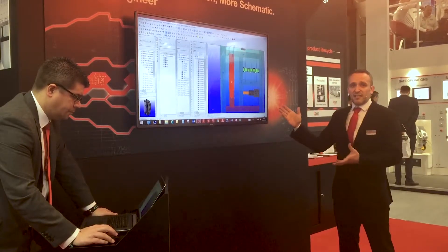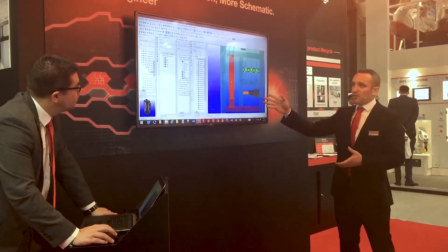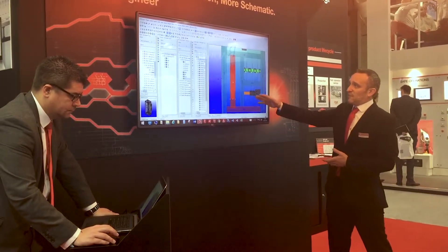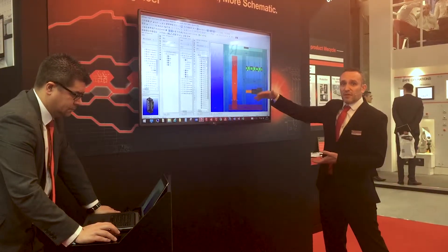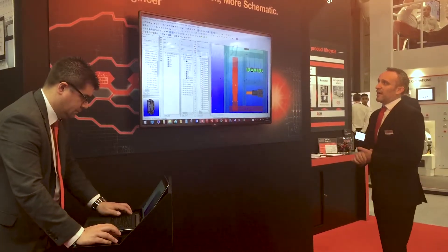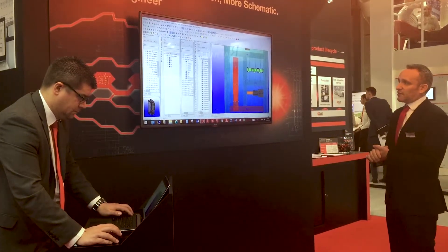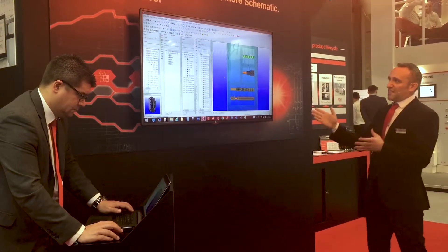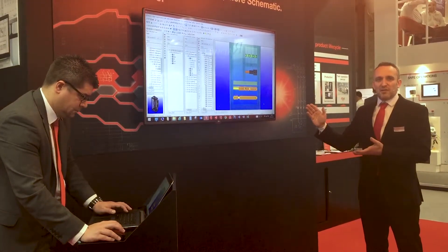If we visualize this — normally we'd say OK, I've got my drive in there — but the SEW is saying there should be a mounting clearance here, an air gap for cooling, and it's not letting us drop this in because our trunking is too close. If you physically looked at it, you would have said we can drop it in, but it's not letting us do that.